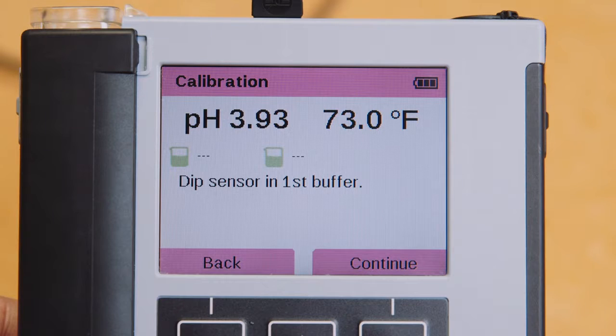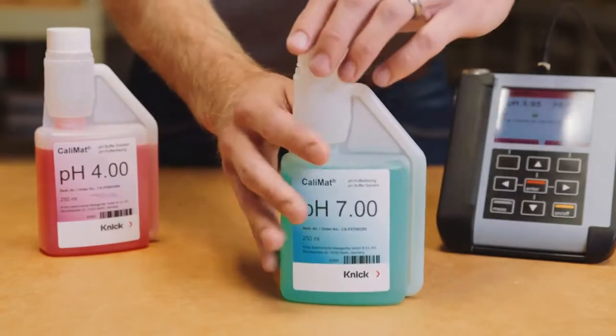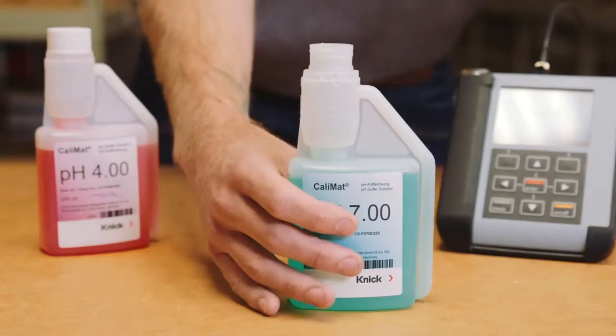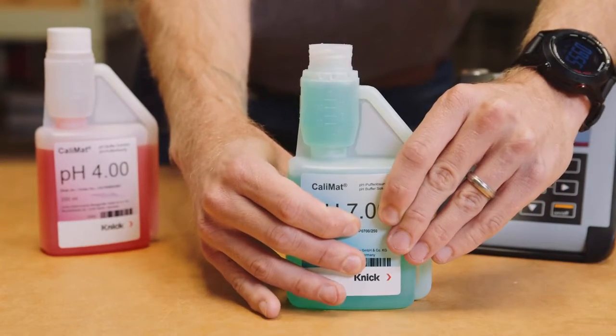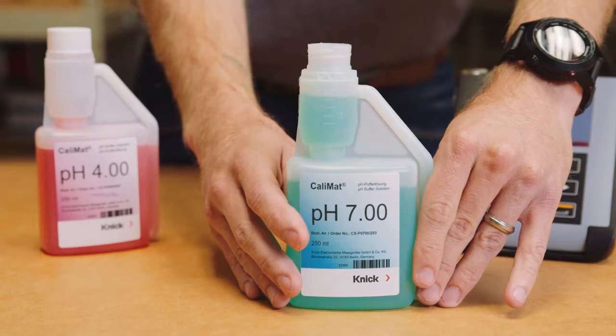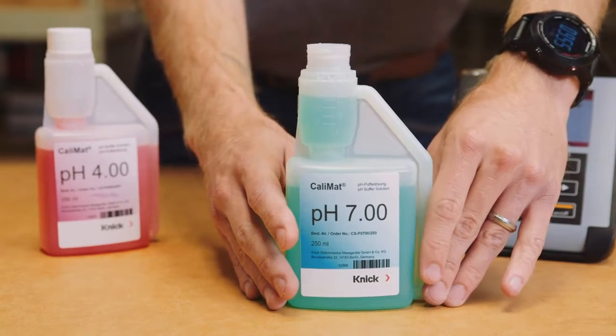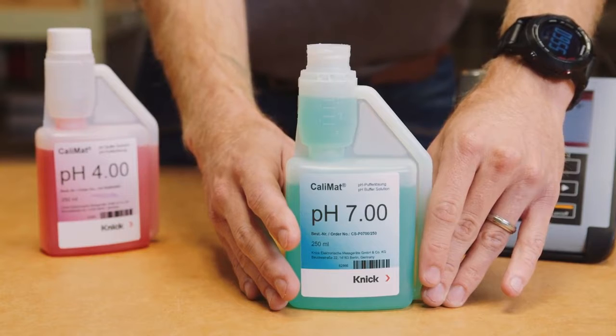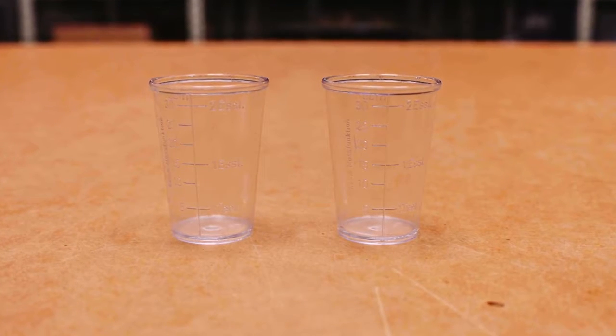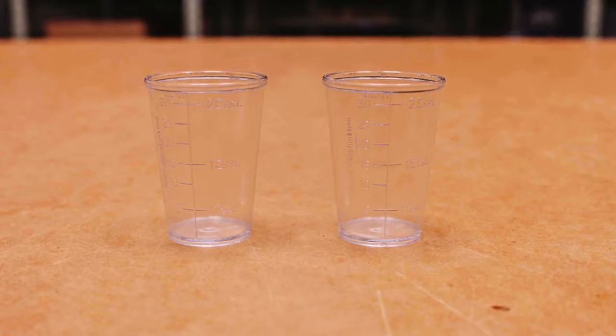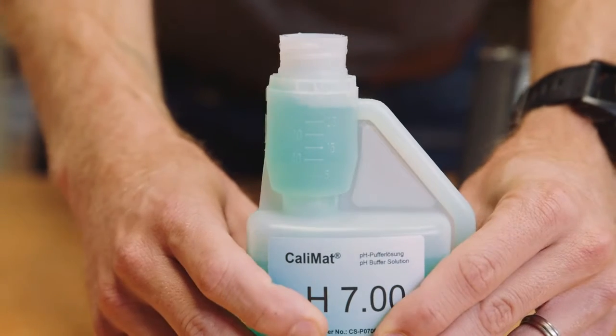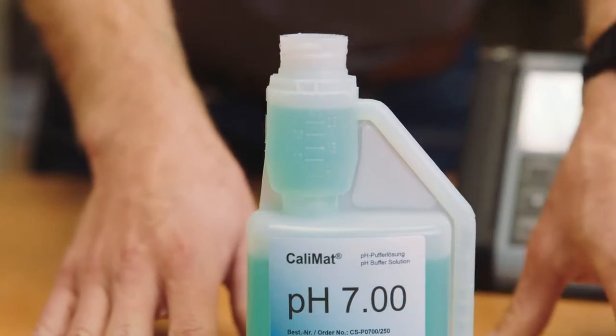The calibration process on the Portavo 907 Multi is very intuitive and straightforward. It prompts you to dip the sensor in the first buffer solution. With automatic calibration, it does not matter which buffer solution you start the process with. I will begin our calibration using a buffer 7. I'm using the CaliMat buffers, which utilize an integrated dosing cup on the top of the bottle for single dose usage. If you're not using CaliMat buffers, put your buffer in a separate container for accurate calibration and to prevent cross-contamination. It's recommended to use fresh buffer solution for each calibration to ensure accuracy.